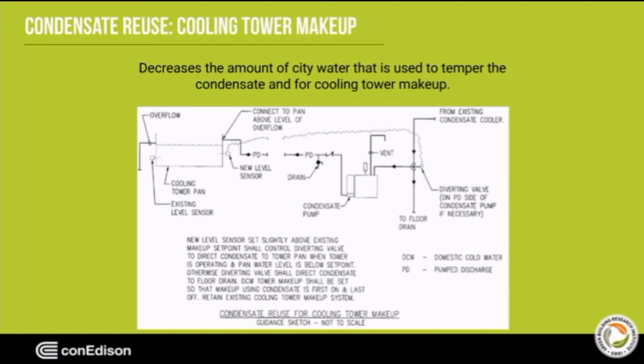Another reuse of condensate is for cooling tower makeup. The use of condensate as cooling tower makeup decreases the amount of city water that is used to temper the condensate and for cooling tower makeup. The total amount of water drained into the sewer is also reduced. As indicated in the sketch, this method will require piping, pumps, and a diverting valve. Both of these methods result in reduced consumption of city water. In both cases, condensate should be tempered with city water prior to use. Hence, the plumbing systems would have to be modified accordingly.